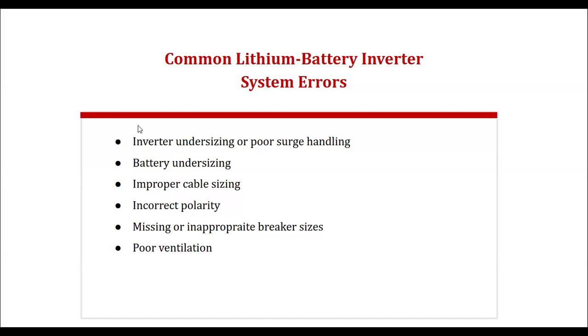It's not that some of these inverters don't have protection, but they have. But when they fail, if you don't have double protections, within a short time you just discover that something has happened. Then you start going up and down, transport, distraction here and there. Poor ventilation. If you keep them in a hot environment, they'll be complaining. Both the inverter and the battery can complain, I can tell you. And if they complain and nothing is done to cool them, they shut down. So please, it's important to follow all this.